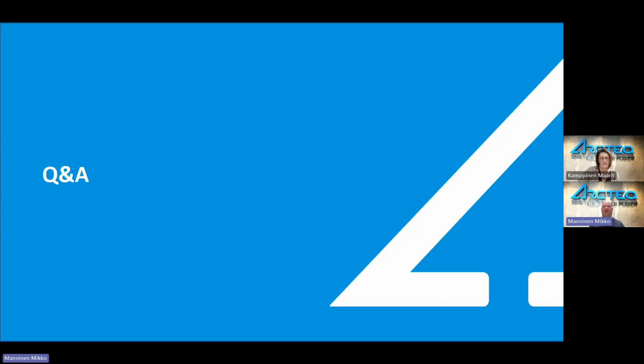Yes and no. Harmonics can be bad for current transformers and also for Rogowskis. But the harmonics are mainly filtered out inside the relay. Whatever signal we get in is filtered inside the relay. So I would say yes and no. I always take every harmonic very seriously, and that's why we filter EMC, EFD and harmonics within the relay.